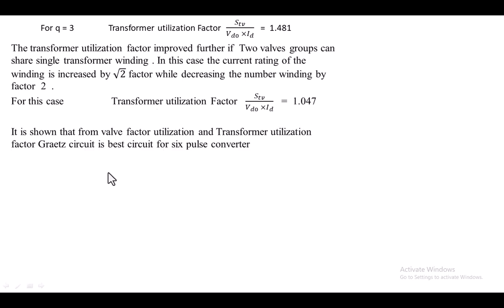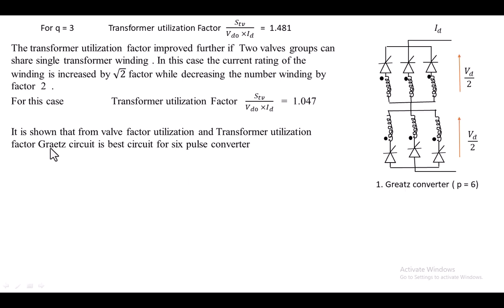We thus achieve better valve utilization as well as transformer utilization with q = 3, r = 1, and s = 2. With this combination, the converter formed is the Graetz converter. It has one commutation group and another commutation group — two commutation groups connected in series. Each commutation group has three devices, hence q = 3, s = 2, and r = 1 meaning only one parallel path. This converter gives a 6-pulse output for the DC voltage.